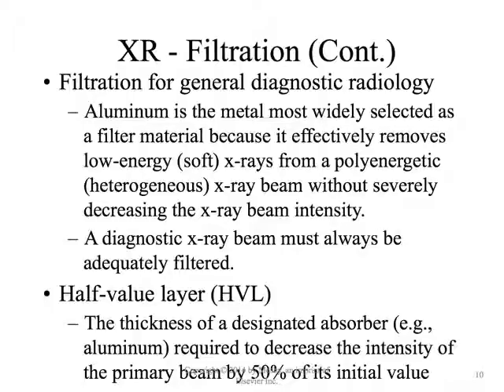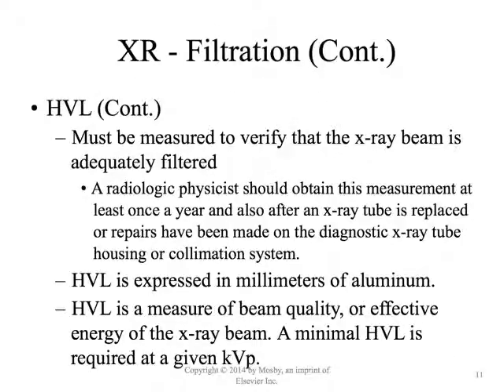Again, we'll use aluminum because it effectively removes those low energy photons, and it's based on the half value layer of the diagnostic energy range of the machine. Half-value layer is the number one way that we can define X-ray quality: what is this photon's half-value layer? As the photon's half-value layer increases, so does the quality of that photon. This is a measurement that our health physicists will do once a year to determine, is the overall energy of the X-ray beam consistent with what's being said at the control console. It's typically expressed in millimeters of aluminum equivalent, and it's the best way to define beam quality.